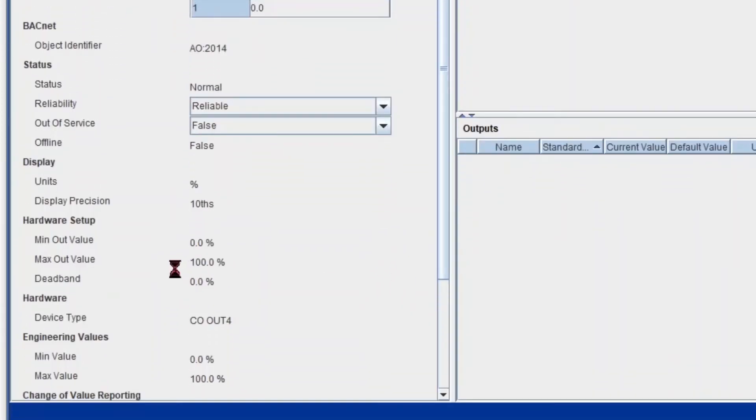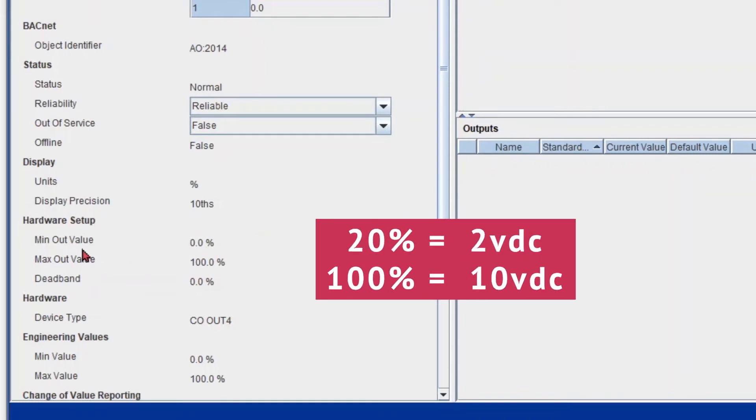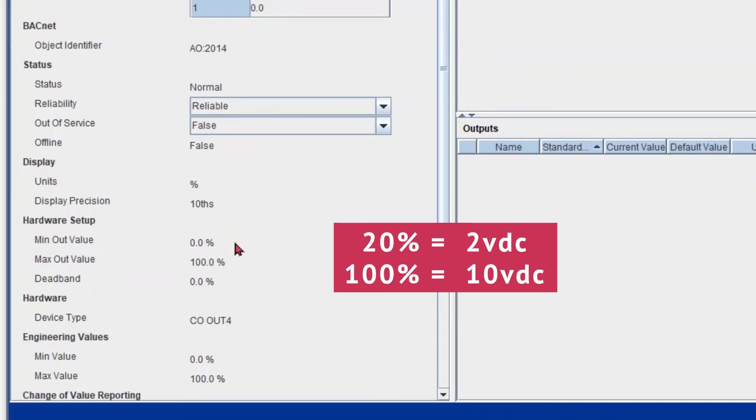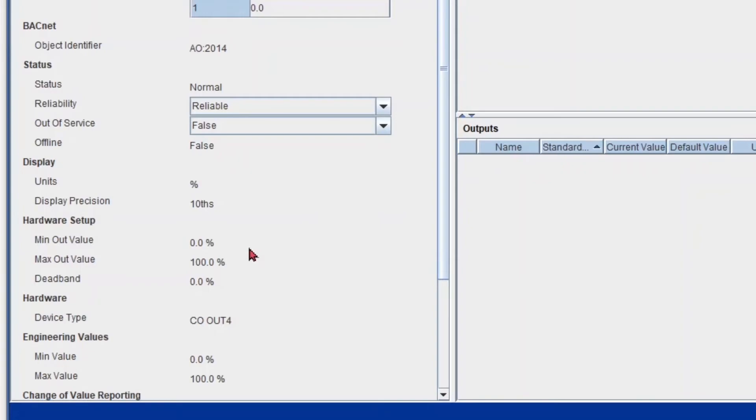And you know how to fix it. So you know that under my hardware setup, in order to make it 2 to 10 volts, we must set my minimum output value to 20% and my max to 100%. But in this case, we have 0 and 100, which means 0 to 10 volts. So we want to change my 0% or my minimum to 20. So it's equivalent to 2 volts. So let's do this from Metasys.